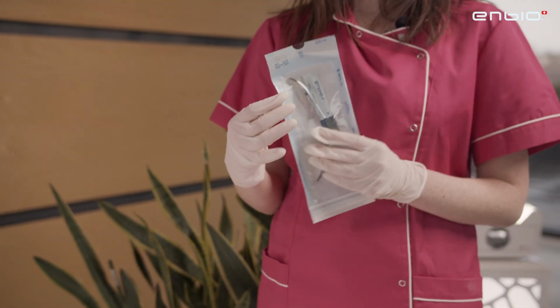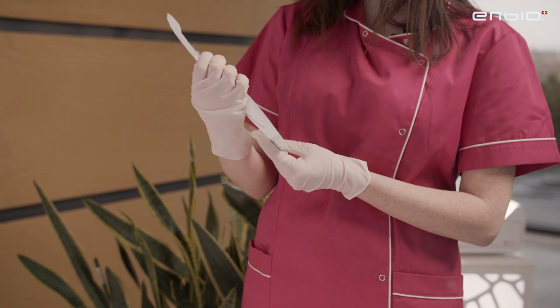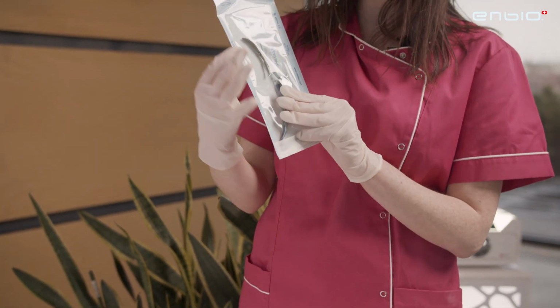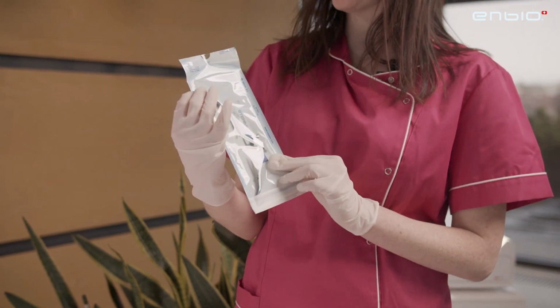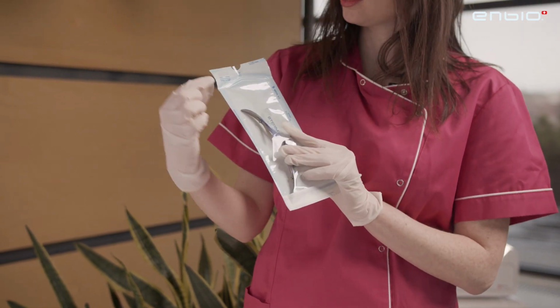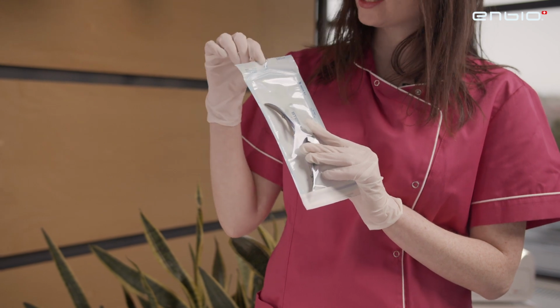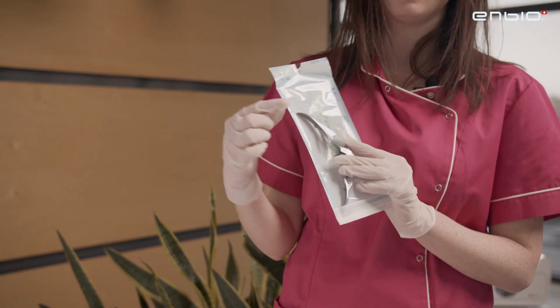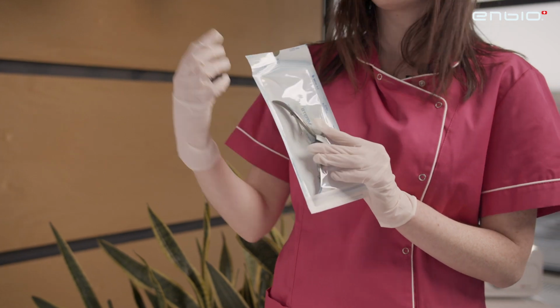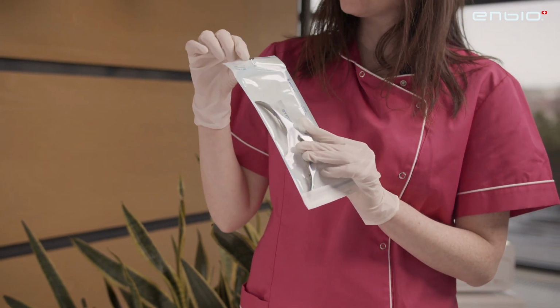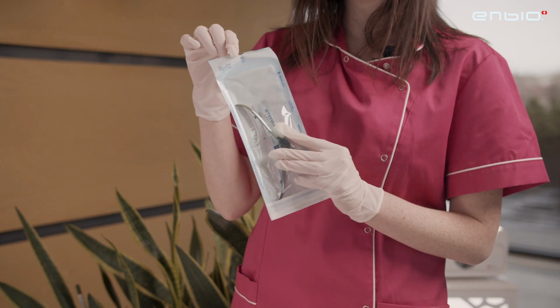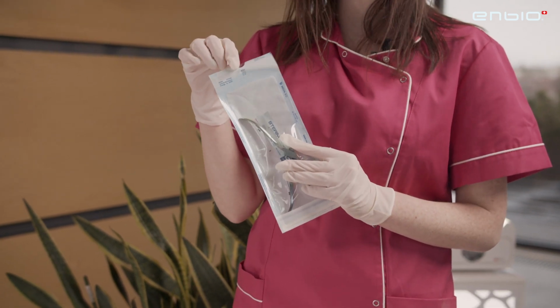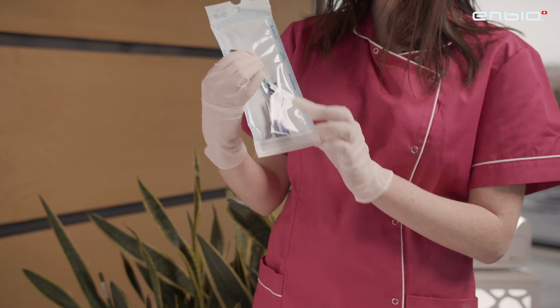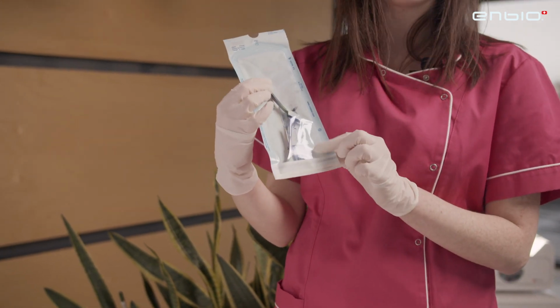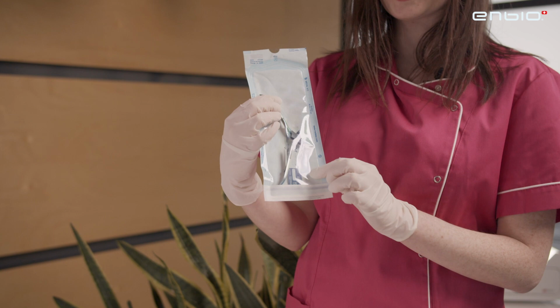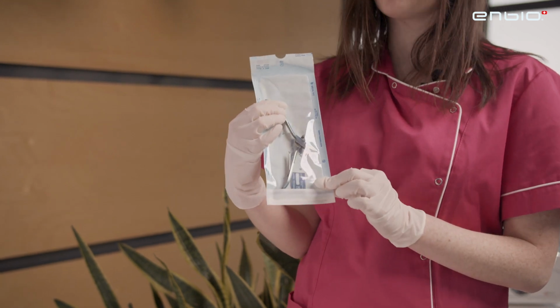So now the tool is ready to be introduced in the autoclave. Once again, I remind the fact that the sterilization pouch already has a chemical indicator. So here we can see that this sterilization pouch is to be used in an autoclave, so in a sterilizer with the steam technology. But this indicator is only class 1 and is not sensitive to all the factors involved in the sterilization pouches, and that is why we prefer to use another chemical indicator to prove the efficiency of the sterilization from all points of view.